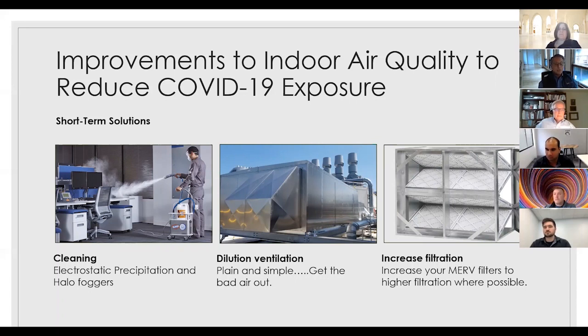The other thing that should be done now and done consistently is dilution ventilation. Plain and simple, get the bad air out. You should be working with your building operators or landlords about having them deactivate demand control ventilation to increase outdoor air to 100% when exterior conditions allow for that. We recognize there's an energy hit on this, and that may be difficult for some landlords to handle, but the bottom line is we're focused on safety now, and that takes precedent going forward. So dilution ventilation, 100% outside air when conditions allow, is what you should be doing at all times, and certainly when the building is unoccupied.